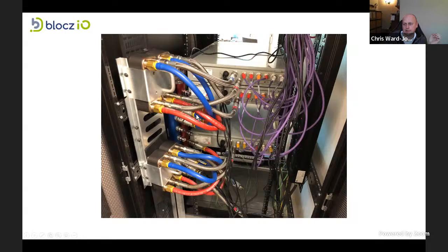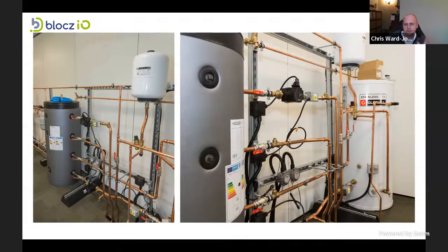And then the heat exchanger is also connected to this manifold, which you can see here. If we had heat exchangers inside the box, we'd just connect them direct to the manifold. The manifold is connected to the heat recovery system, which effectively draws the heat out of the heat exchangers. It doesn't look very shiny, granted, but we built it like this so people could see it, touch it, feel it, and understand how it works.